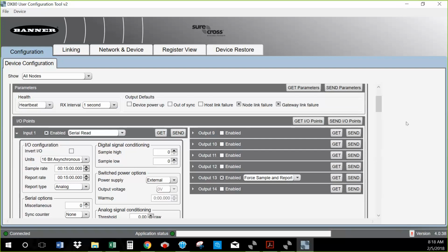It's been my experience with temperature and vibration, which has been a very good seller in our area. We've done a great job with that product. The territory managers and the distributors in my area have done a really good job bringing that out. We've had good success with it. What I found is that most customers are checking their motors, their vibration and temperature, at best every 30 days, sometimes 60 or 90 days. So we're taking them from a place where they were doing monthly, bi-monthly, 3 months, twice a year, to every 15 minutes. So that's a pretty good step forward.